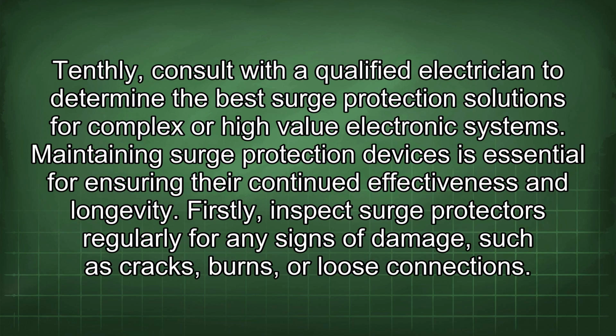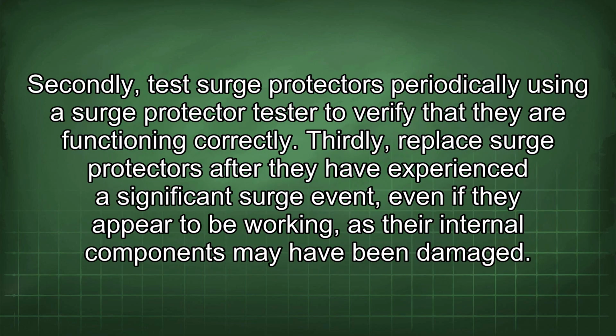Tenthly, consult with a qualified electrician to determine the best surge protection solutions for complex or high-value electronic systems. Maintaining surge protection devices is essential for ensuring their continued effectiveness and longevity. Firstly, inspect surge protectors regularly for any signs of damage, such as cracks, burns, or loose connections. Secondly, test surge protectors periodically using a surge protector tester to verify that they are functioning correctly.